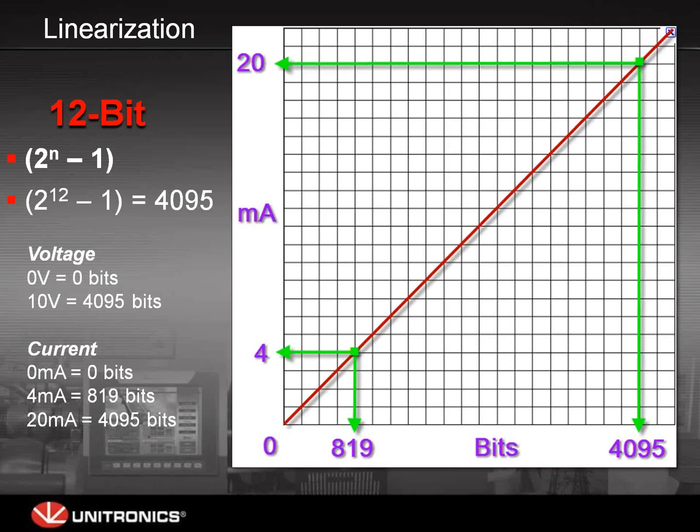The value that comes into the controller will be in bit values. If we have zero volts on our sensor, the operand assigned in VisiLogic will also have zero in it. Zero equals zero bits. If you have 12-bit linearization and 10 volts on the sensor, inside the register in VisiLogic it will display 4,095 bits.